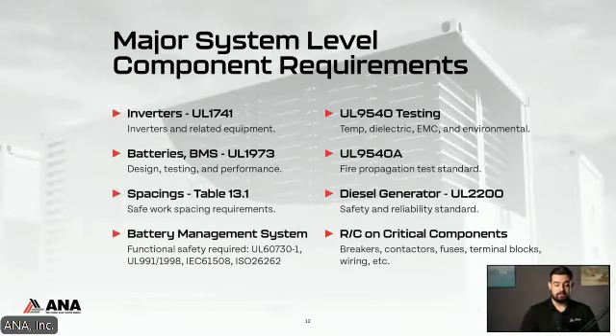And then recognized components on all critical components. So this is kind of what I touched on earlier. These are going to be breakers, fuses, terminal blocks, your controller. Every component of your system is going to have to be a recognized component if it's deemed a critical component. So as you evaluate your system with your engineer at UL or Intertek, whatever that certification body may be, they will come up with a list of critical components that you will have to have component level certification on.